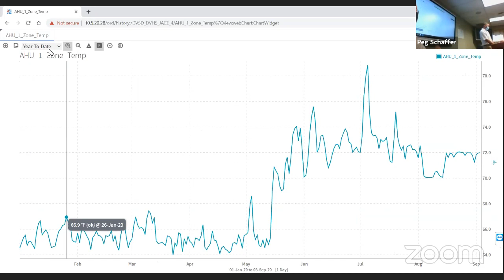For your maintenance folks, if someone is regularly saying it's warm or cold, sometimes you can't tell whether you're actually having a problem at that moment or if it's intermittent. You can start to find these problems using the trend logs. You can actually put multiple trends on the screen at one time and follow the water valve, what it's doing, the damper, what it's doing. Oh wait, that water valve isn't supposed to be open at that time - you can see something happened there. You can troubleshoot to the point where you almost know what the problem is before you even get to the room.